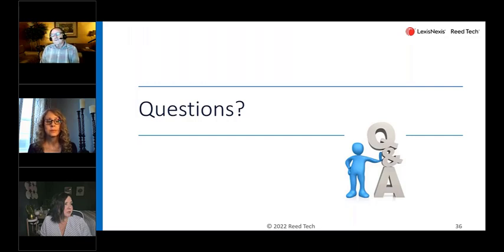Wow, I think I'd follow some of the guidelines that Linda put in place there. There is another pretty detailed version of that that we'd be glad to share with you. You can contact us and we'll go through some steps about creating a UDI system. There's a number of aspects, and those 5 steps are developed much more in detail: preparing the team, understanding what you have to do, and then making sure you have a platform in place. In parallel, if you don't already have an account, I would highly recommend you create an FDA account. And if you're going to be submitting electronically, there's a second step to do some testing. If you engage Reed Tech, we take care of that and do that for you.